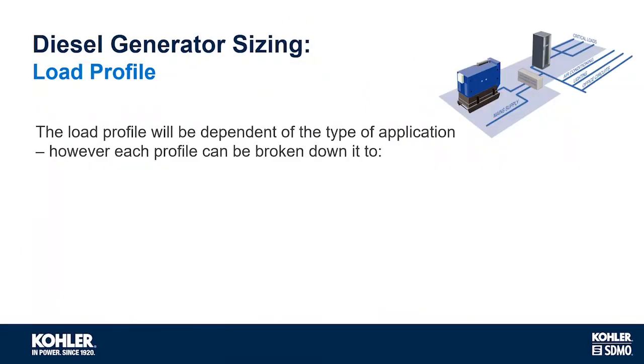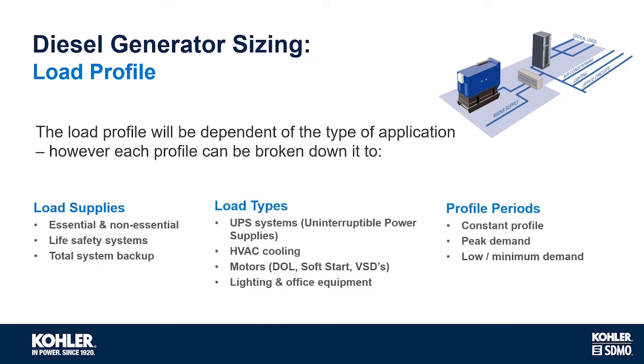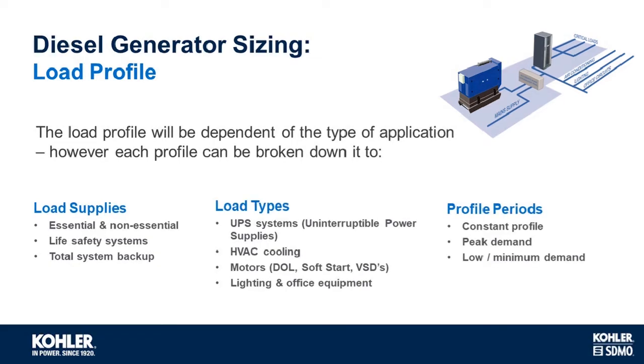The load profile is an important point, as this can change the rating and duty type that should be applied. The profile can be broken down as follows. The load supplies, so the split between essential and non-essential, as non-essential loads might not need to be supported by the generator. Is the generator supporting life safety systems? Because this may need to be connected first. And of course, the total system load.